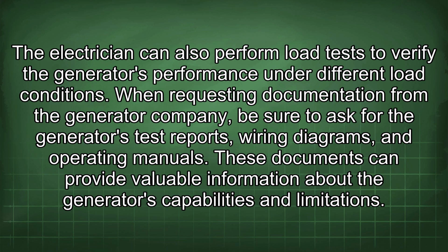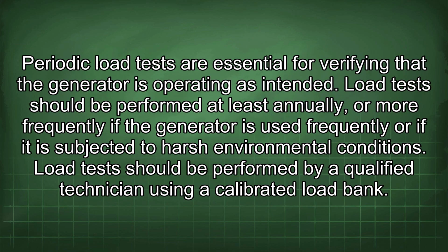When requesting documentation from the generator company, be sure to ask for the generator's test reports, wiring diagrams, and operating manuals. These documents can provide valuable information about the generator's capabilities and limitations. Periodic load tests are essential for verifying that the generator is operating as intended. Load tests should be performed at least annually or more frequently if the generator is used frequently or if it is subjected to harsh environmental conditions.